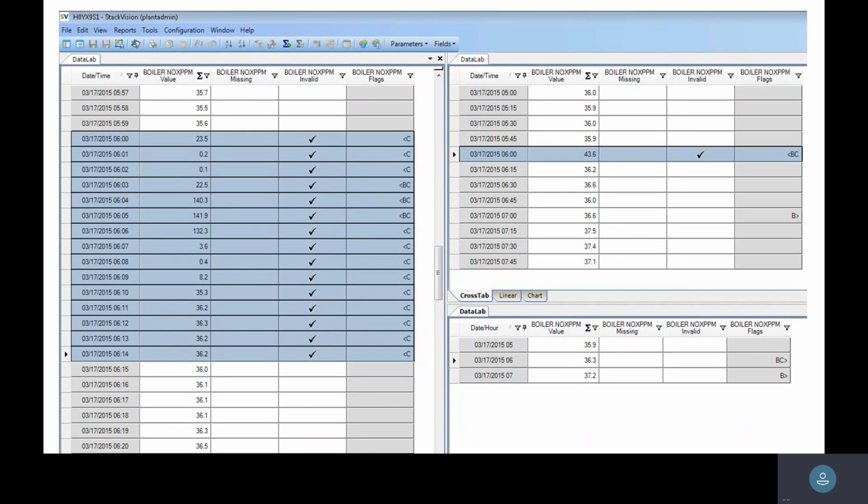So this is just a quick example. At a glance, I can see the parts and pieces that build up to that 1-hour average or that 15-minute interval that I have to report, or am not able to report because I don't have enough valid data to support it. And this is where DAS excels. DAS can understand these pieces and rolls these data values forward. You don't have this granularity traditionally in a historian or in an EMIS system, especially not for 5 years. That would be huge in terms of size, in addition to everything else those systems are recording and tracking at this point.